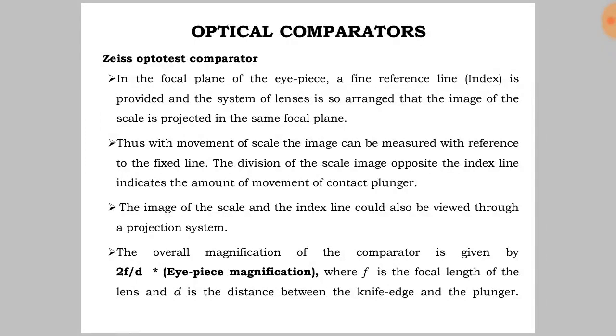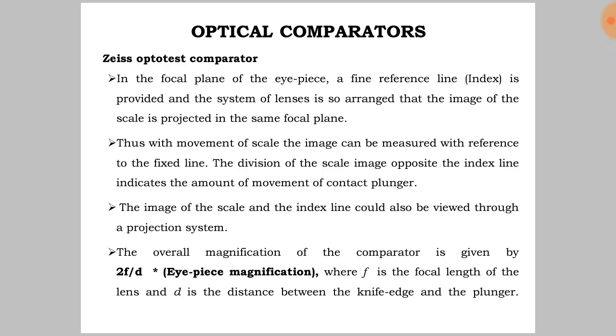The image of the scale and index line can also be viewed through a projection system. The overall magnification of the comparator is given by 2f/d times eyepiece magnification, where f is the focal length of the lens and d is the distance between knife edge and plunger. This is a short video about Zeiss optical comparator and Zeiss optotest comparator.